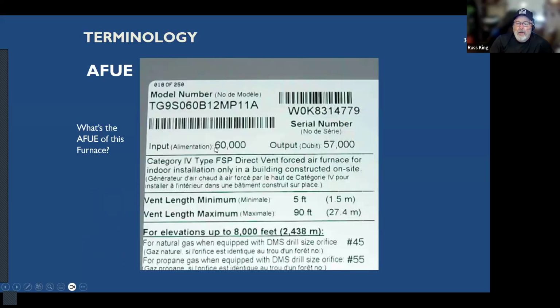Okay. So here's one. We're putting in 60,000 BTUs of gas, and we're getting out 57. Ooh, that's pretty good. That's a much higher efficiency furnace. And this is probably a condensing furnace. And 57 divided by 60 is 95. So this is a 95% furnace. That's pretty good. They're getting up into the 96, 97% ranges, some of the highest ones I've seen. That means they've just figured out how to capture that heat that would otherwise be lost. So there you go.